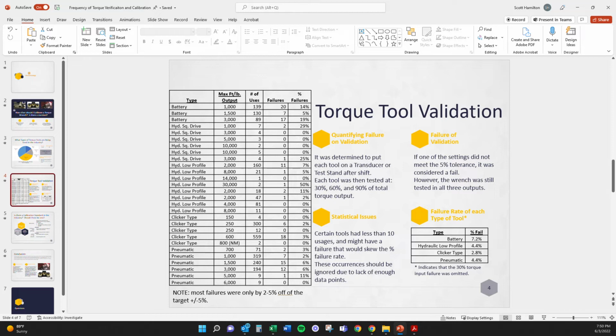And we found that basically everything ends up being around this 5% failure. You see batteries were a little bit higher, and the reason why is we were using them at their low end. You should always use tools that are between like 30 and 80% of their stated range. That's where their wheelhouse is. You start getting below the 30%, you're going to start seeing a couple where it just doesn't end up being that plus or minus 5%, right? It's just a little bit off there. So we saw a couple of those. So that 7.2, I'm not worried about it. That should probably drop down to about 4%.